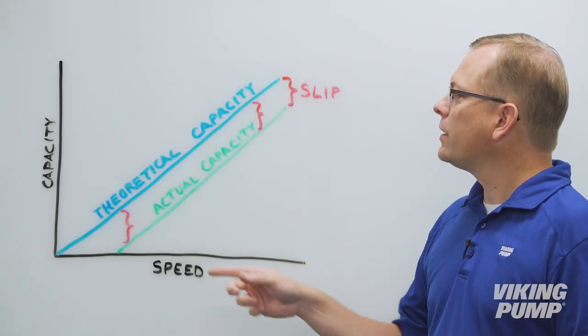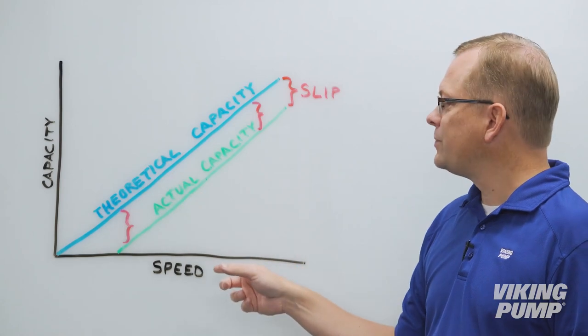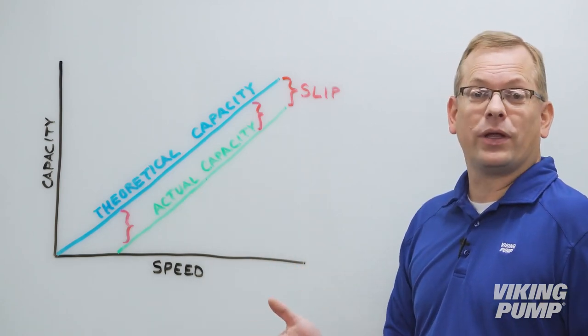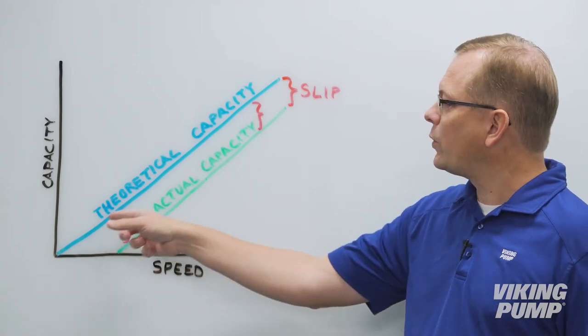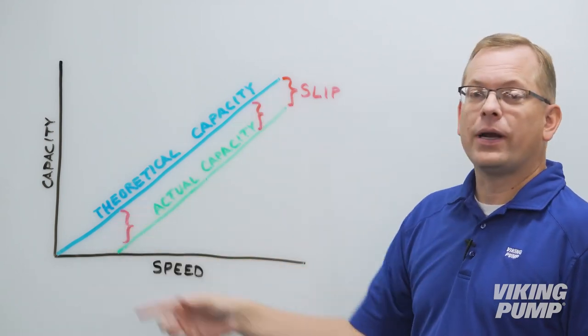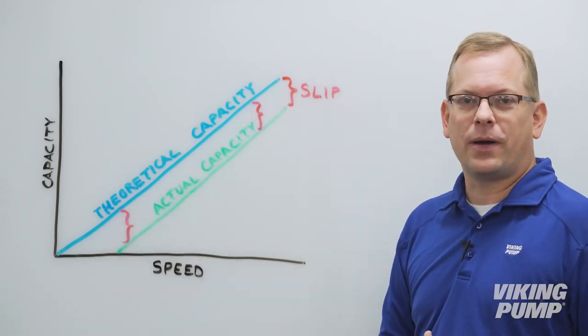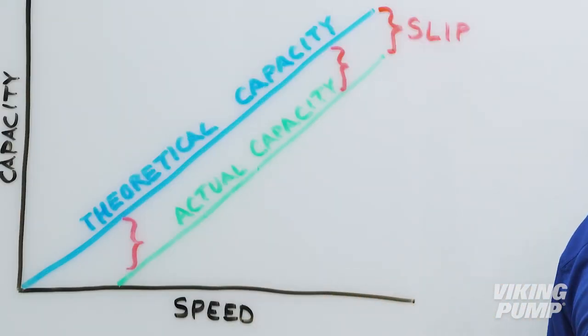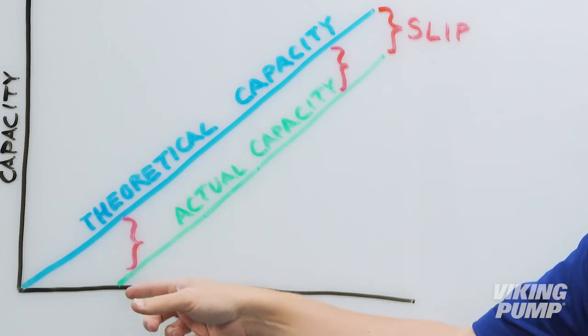So here I've made a chart of capacity versus speed. Using the equation of displacement times speed equaling the theoretical capacity, we end up with a line that runs through zero, that is the theoretical capacity for a positive displacement pump. When we subtract slip, we can see that the actual capacity runs parallel to that, but does not cross through zero.